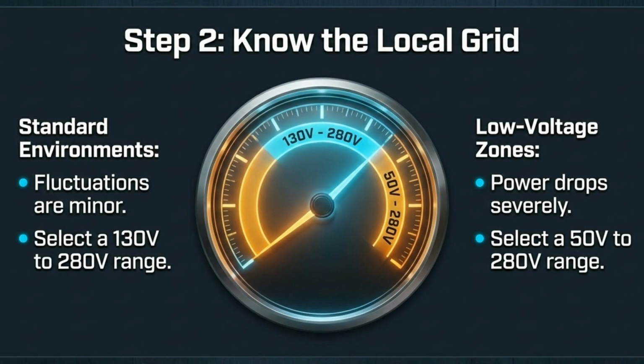Step 2 is knowing your local power grid. In standard environments with minor fluctuations, a 130 volts to 280 volts range is adequate. In low voltage zones, a wider 50 volts to 280 volts range is recommended to handle severe power drops.